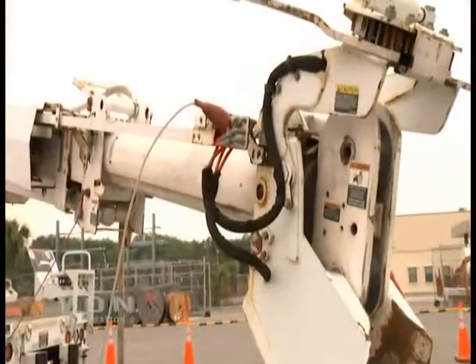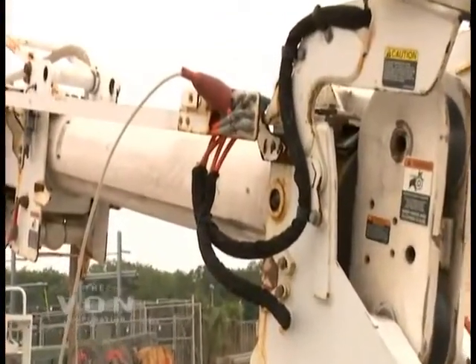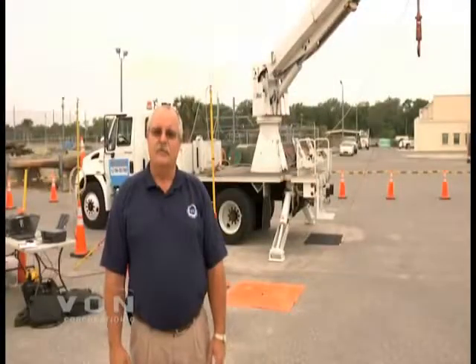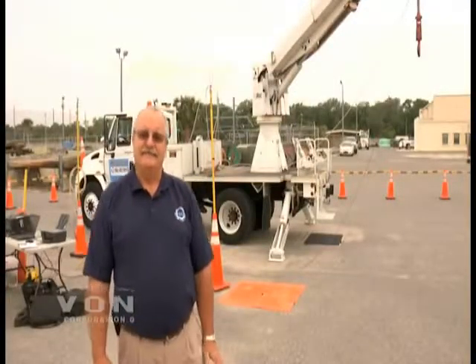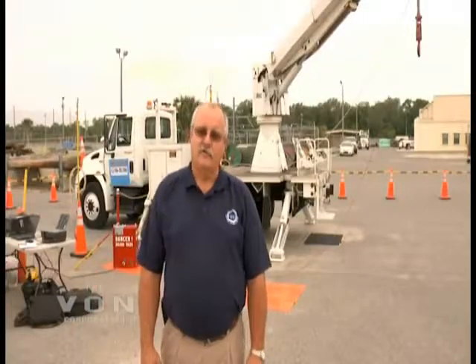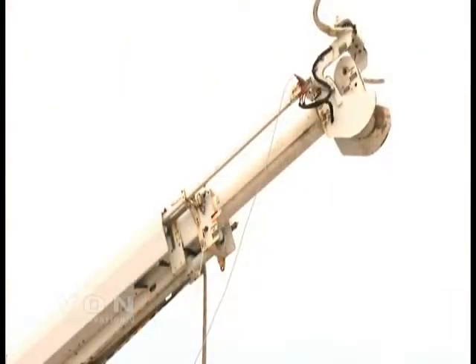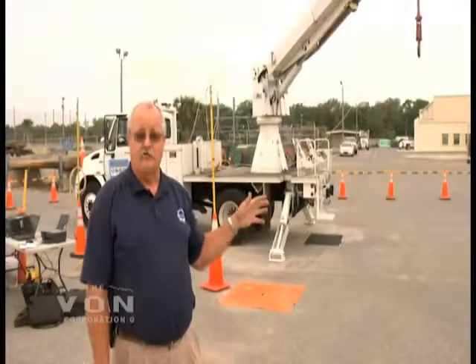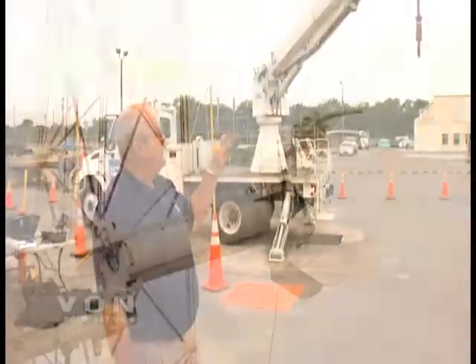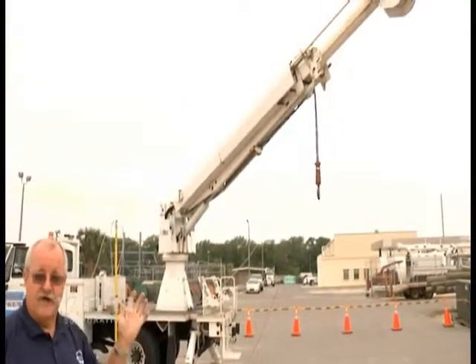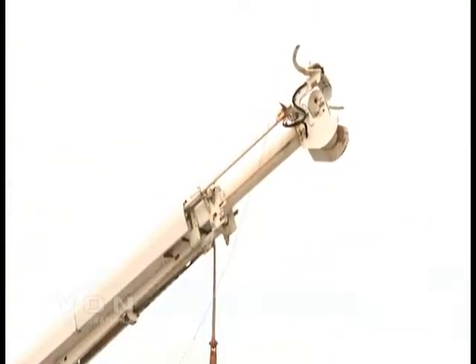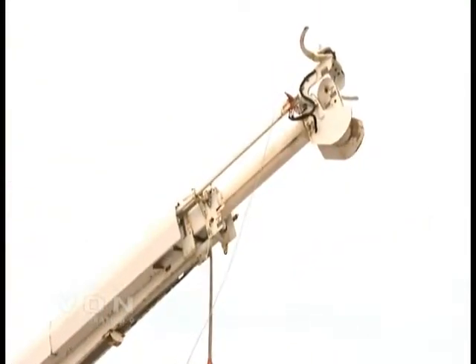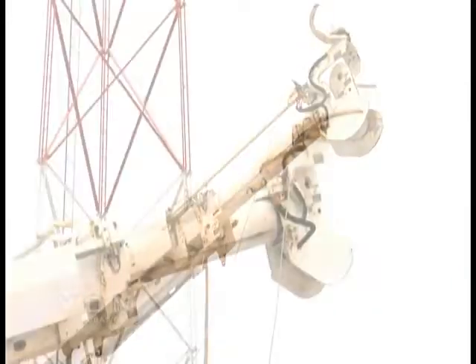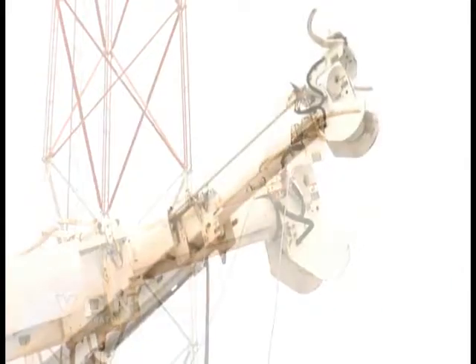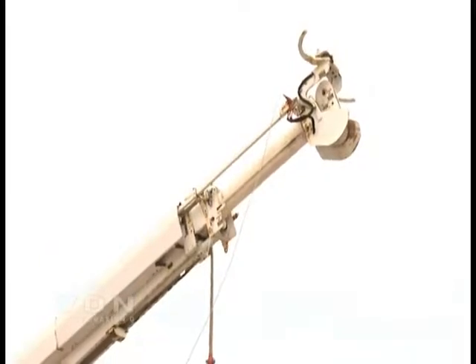This unit is a digger derrick unit. It has been insulated for 46 kV, so we will be testing this unit at 56,000 DC for 3 minutes. We have removed the rope as the ANSI standard calls for, and we have scoped the boom out to where the insulated arrows are. We did not go any further than what the insulated arrows call for. We have grounded the metal part of the boom, and we are going to energize the metal part of the insulated boom, and we're going to energize the hydraulic line cat track that's got the insulated hydraulic lines in them.